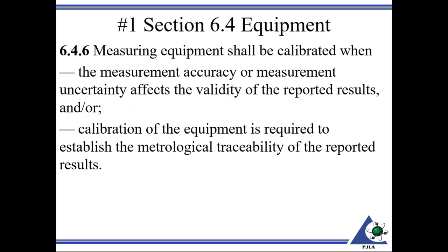Equipment calibration. So it may also crosswalk into traceability here. Your equipment has to be calibrated when the measurement accuracy or measurement uncertainty affects the validity of the reports and where metrological traceability is needed. So if it's needed in order for a traceable measurement to be supported, that equipment needs to have a traceable calibration report to accompany it.